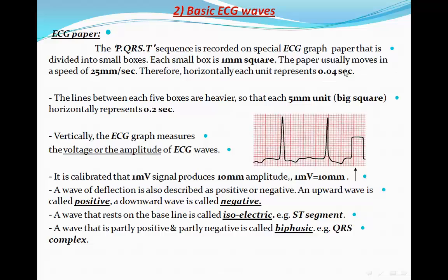Vertically, we are talking about voltages. The ECG machine is standardized so that every one millivolt of electrical stimulation produces 10 millimeters in height. This is called the standardization mark. It can appear automatically on the ECG paper, or it can be produced by pressing the one-millivolt button found on many ECG machines. By pressing this button, you produce a one-millivolt electrical stimulation and then check whether the resulting mark covers 10 millimeters in height — confirming that your standardization is correct.